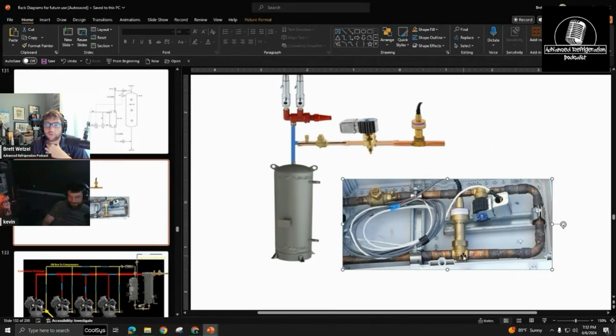So if you were to just limit the opening percentage to, let's say, 15%, you'd at least keep pressure on this side of the pipe before it's able to relieve. Essentially you'd have way less chance of creating dry ice.